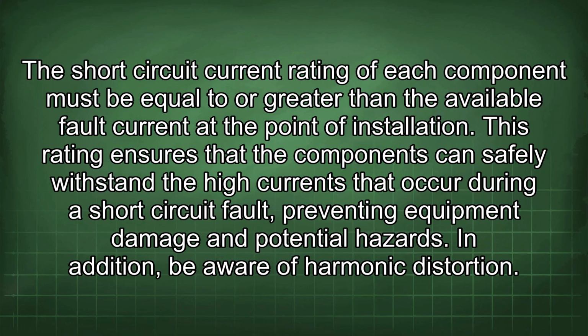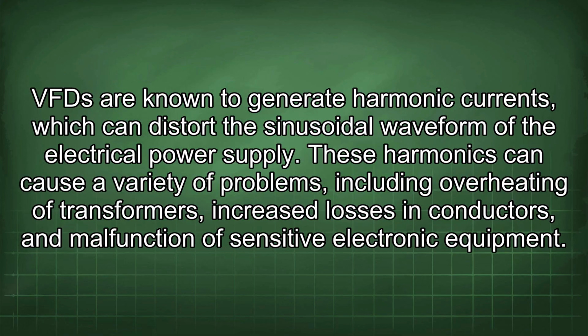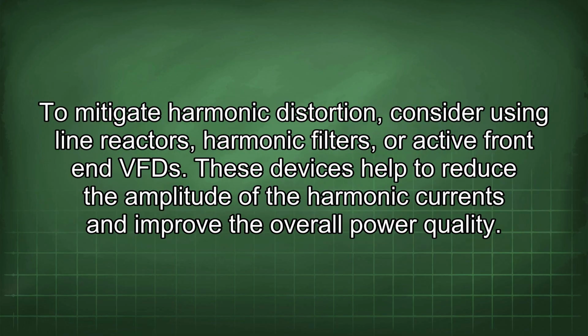In addition, be aware of harmonic distortion. VFDs are known to generate harmonic currents, which can distort the sinusoidal waveform of the electrical power supply. These harmonics can cause a variety of problems, including overheating of transformers, increased losses in conductors, and malfunction of sensitive electronic equipment. To mitigate harmonic distortion, consider using line reactors, harmonic filters, or active front-end VFDs. These devices help to reduce the amplitude of the harmonic currents and improve the overall power quality.